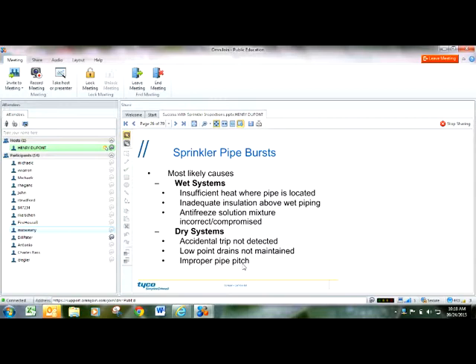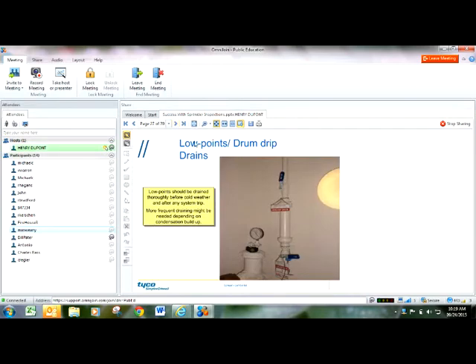So the furthest sprinkler head out on a branch line has got to pitch its way back to the cross main that's pitching back to the riser to the main drain. If you have areas of the system that are trapped, that pipe still has to pitch back to low point drains. This is a dry pipe sprinkler system low point drain, or a drum drip. If you owned a building with a dry pipe sprinkler system and you have these in your building, right now is the time that you really want to go around and start purging these drains to get any condensation or trapped water in your system out, because it's going to get cold.